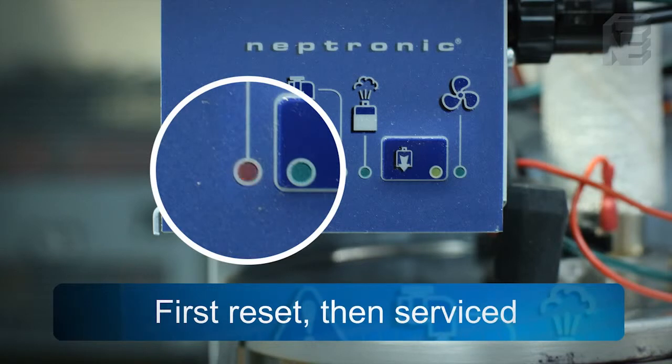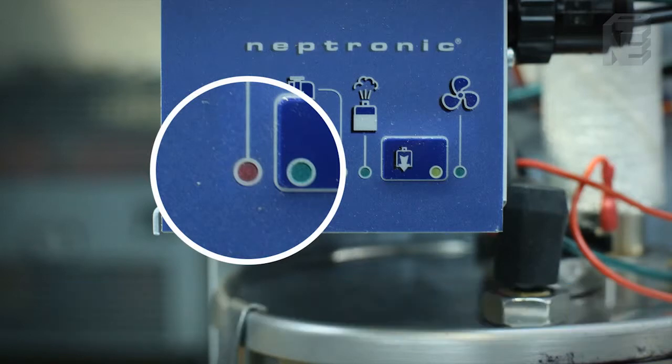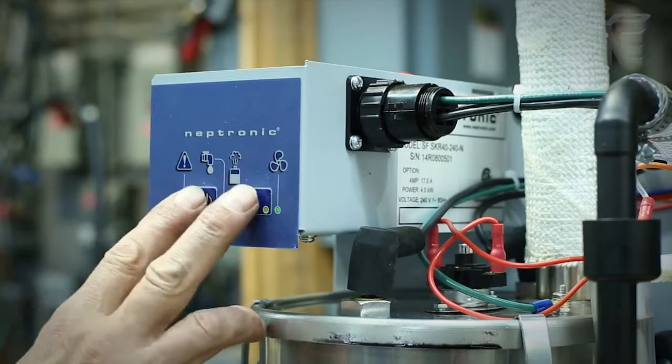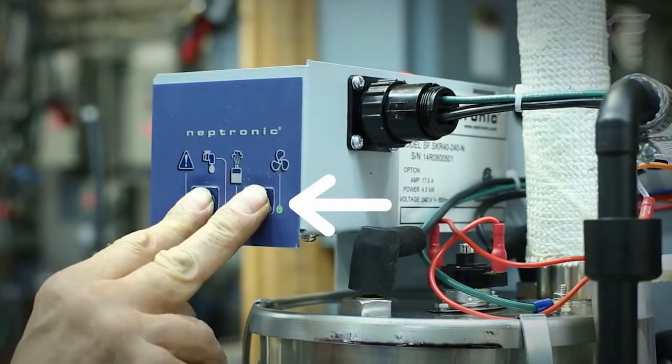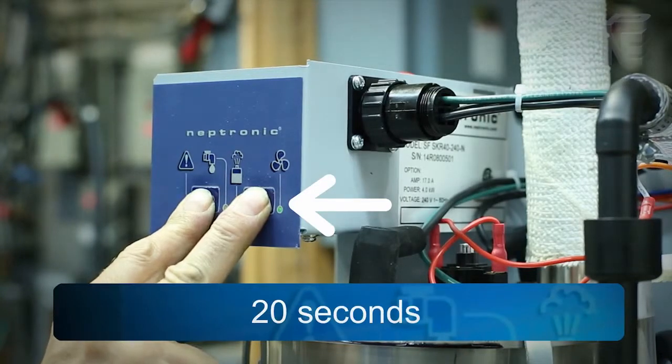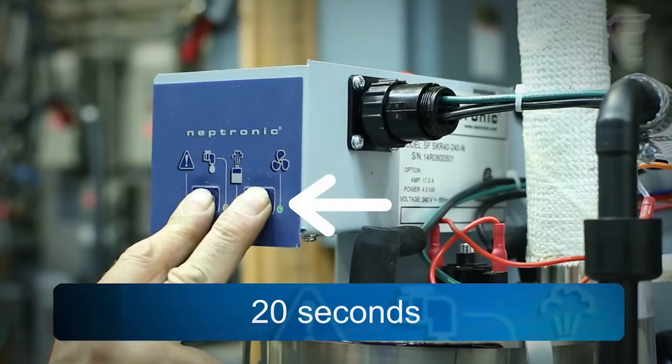Once reset, it will go through another 1,500 hour period of operation. To reset the time factor to zero hours operation, press both the power push button and the drain push button simultaneously for about 20 seconds, and this will zero the hours and get rid of the red check light.